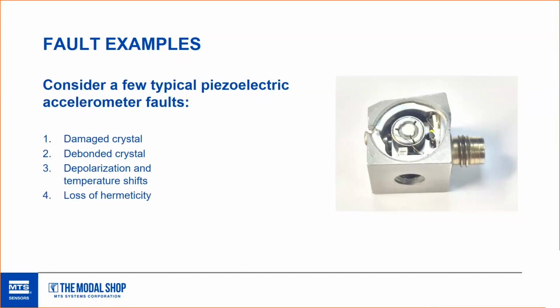Loss of hermetic seal. Generally, a sensor like this may be closed or welded. Damage to that sealing can compromise the low frequency performance, and low frequency scaling issues may occur up to 30 hertz. Think about, again, your handheld calibrator at 100 or 159.2 hertz. Is that going to find it? Maybe not.